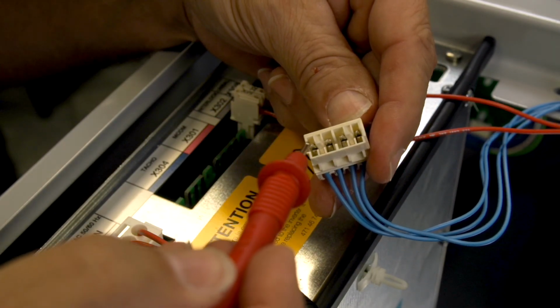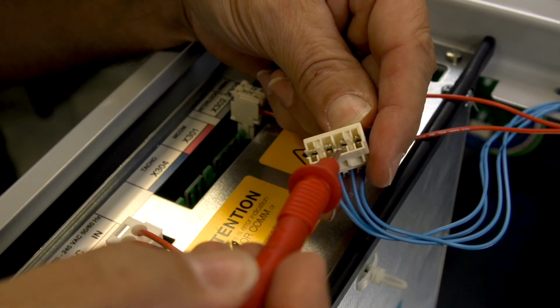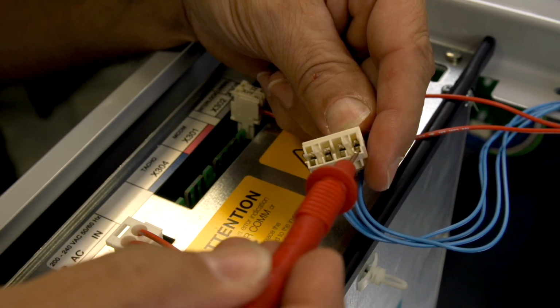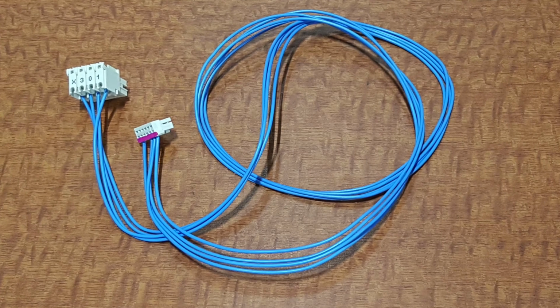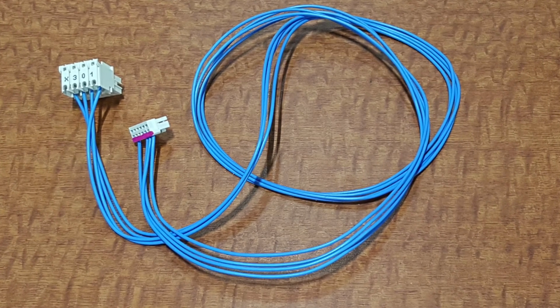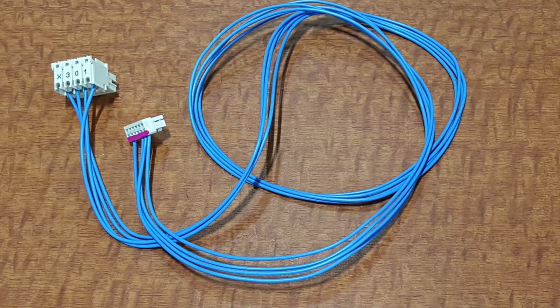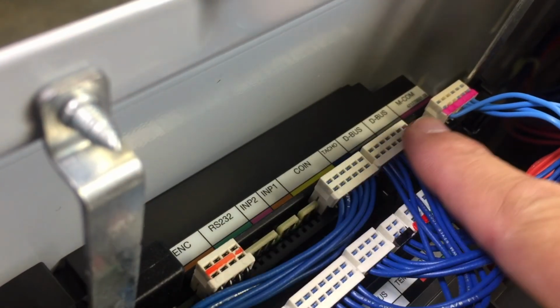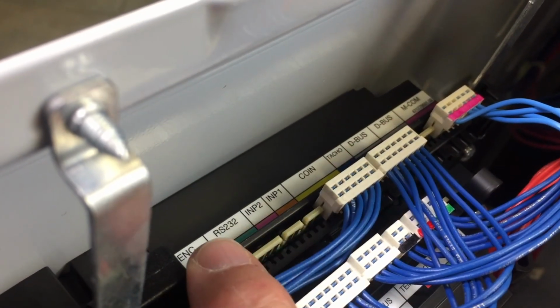To do this, disconnect both ends of the communication harness and test each wire for continuity. If a fault is detected during these tests, replace the communication harness. If the motor communication harness reveals no faults, replace the CPU.